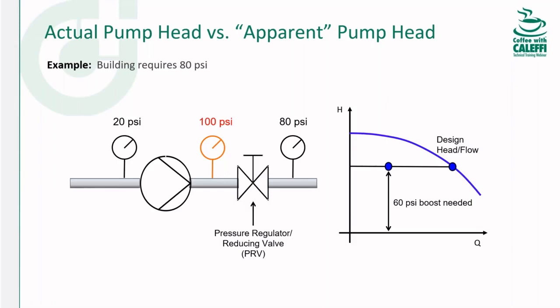So a big mistake made in retrofit situations is using existing pump tag information to supply a brand new booster. And everybody says, oh, it's variable speed. It'll correct itself. It'll right size itself because it's got VFDs. To the point, yeah, that's true. But why pay an extra $10,000 for equipment when you should actually go with what the building actually needs? And in this case, it would be 20 PSI to 80 PSI. So I just want to throw that out there, especially important for retrofit information.